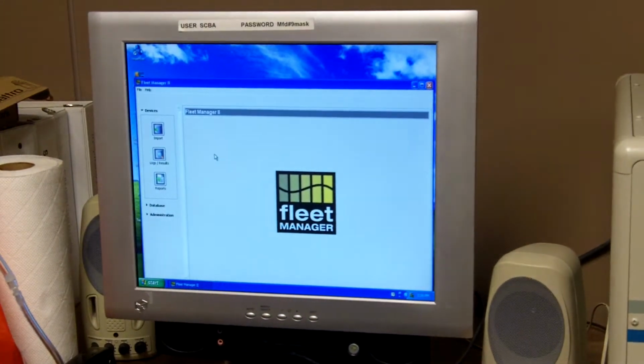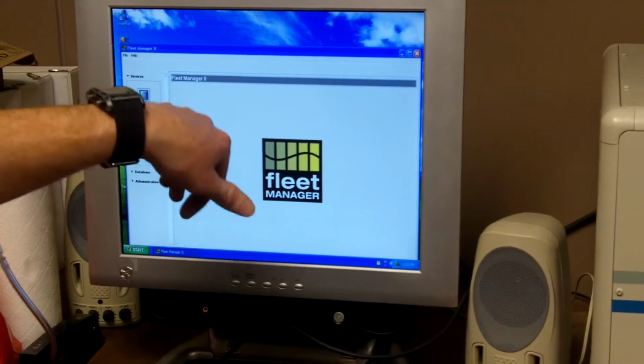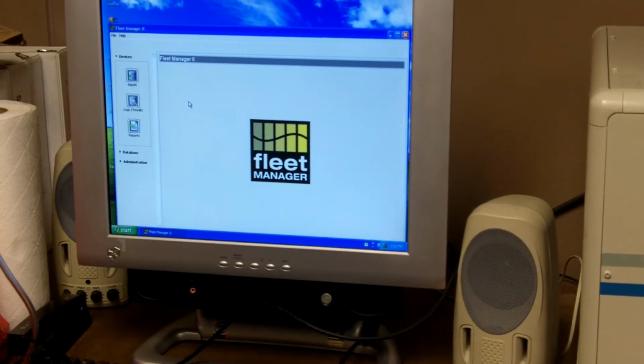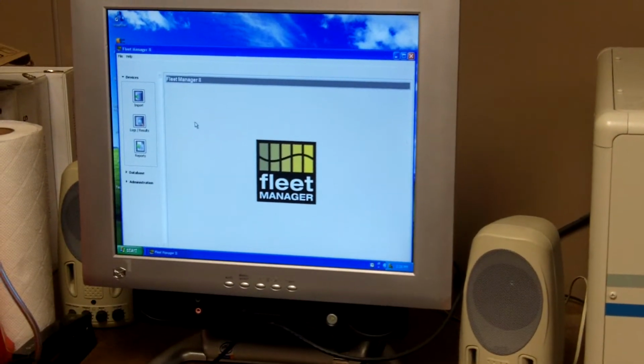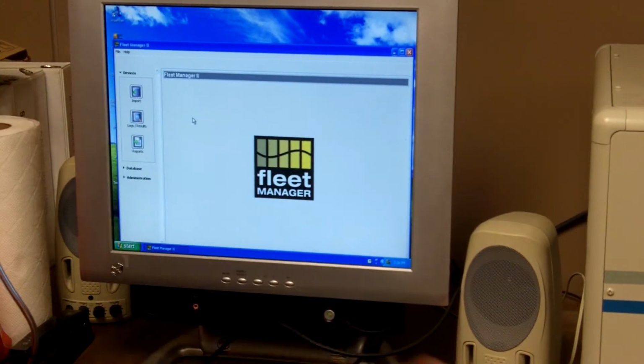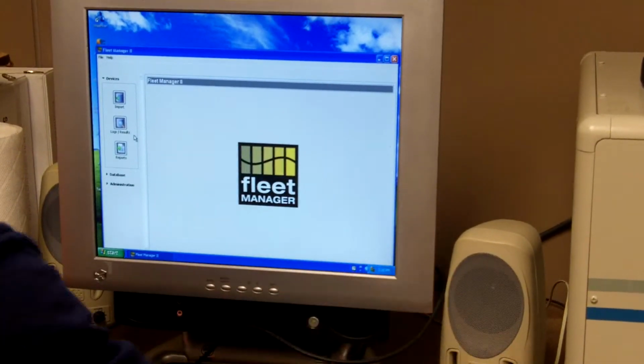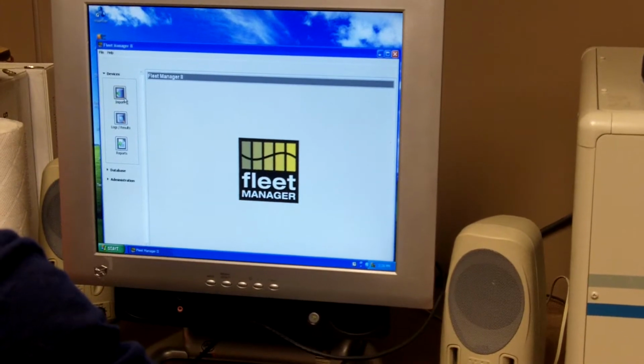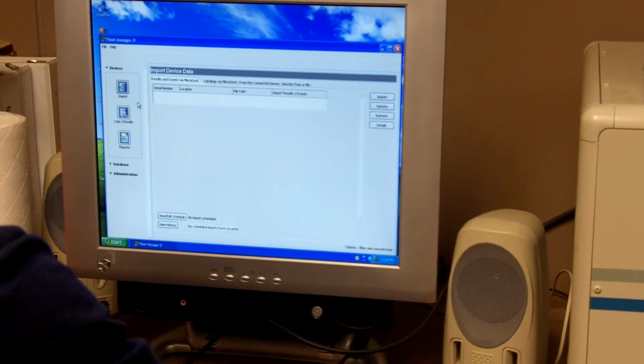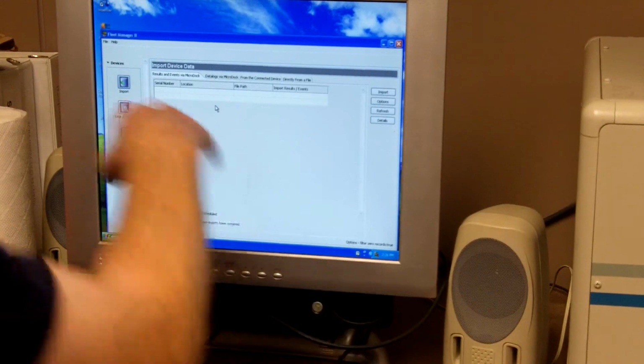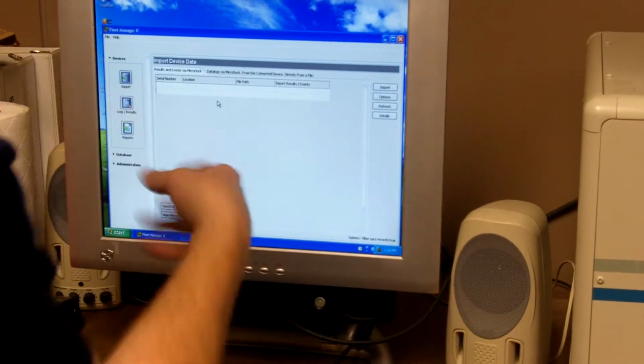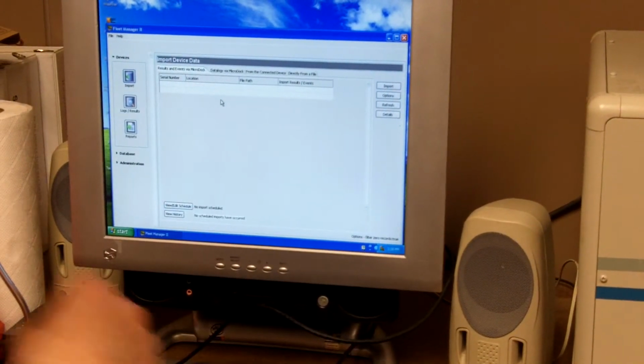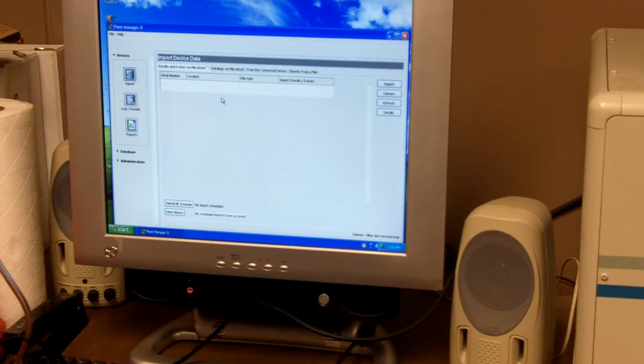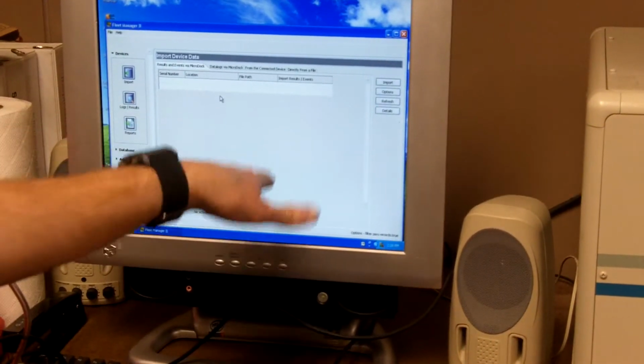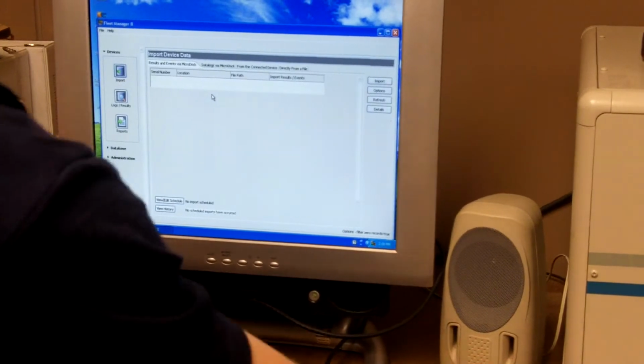So next, while this is calibrating, like I said, I brought up on the computer inside the SCBA room the Fleet Manager 2, and after it's done calibrating, we need to send it to the computer. And the way I do that, I'm going to first open it up, it runs through its checks, and then I'm going to hit import. And then from there, it will say what device is hooked up, and then I'm going to hit import again. And then it will take that information and put it on.